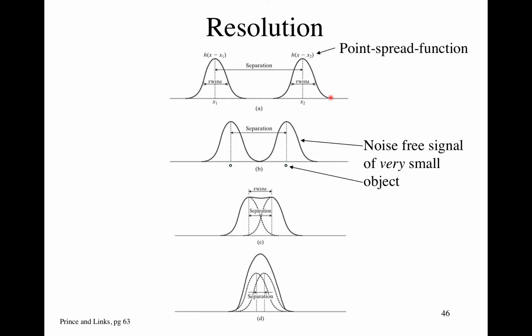That's the point. We're using an impulse signal that's much higher spatial frequency than we can resolve, but you can measure the shape of this curve. And that gives you the underlying point spread function of a delta function or a very small dot in your imaging system. You can imagine that if this width gets wider and wider for different systems, that means it's a lower resolution system. It blurs that signal into a broader spatial distribution. If it's really sharp and narrow, then it's a high resolution system.